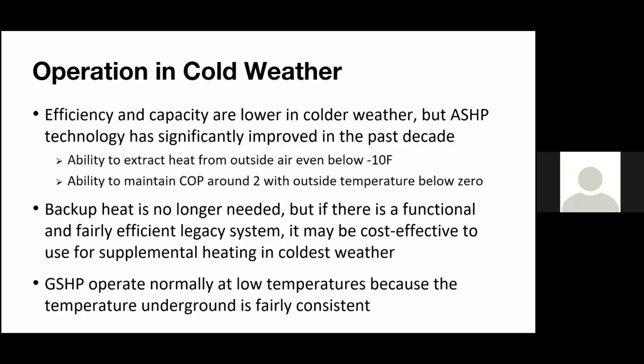Now, any heat pump is pretty much able to extract heat out of the air below -10 degrees. All the split systems have kind of caught up. There are low ambient heating capabilities for split systems, and also VRF technology. The larger ones can go past -25 degrees. They can heat past -25 degrees. And yeah, that's cold, and that's probably not somewhere where I want to be living anytime soon. But as long as your refrigerant is colder than your ambient air, there is going to be some heat extraction with that, while maintaining a COP of around 2. So we're still putting in 1 and getting 2 basically at that 0 degree temperature.